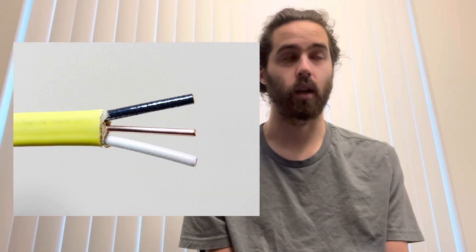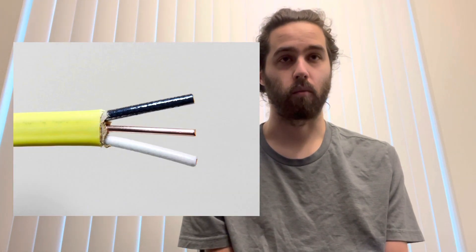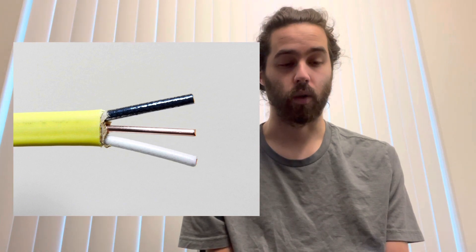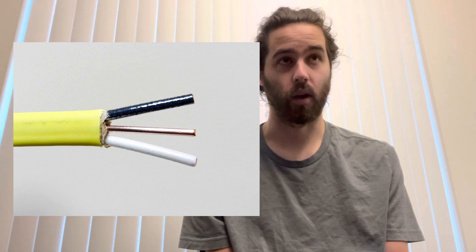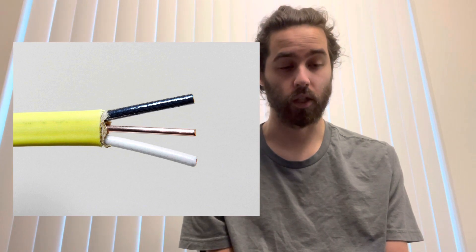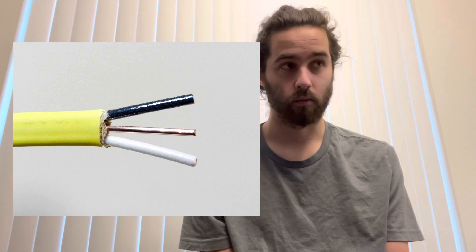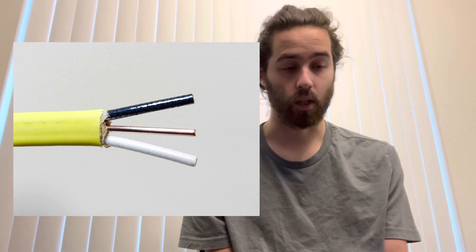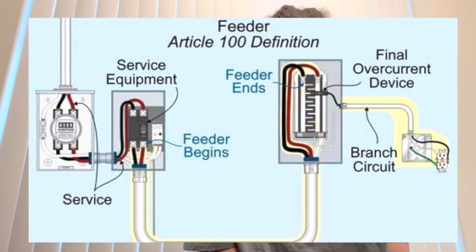Then you've got your hot, neutral, and ground, which are inside the wire — inside your Romex. You've got your black wire, which is your hot; your white wire is your neutral; and your ground is usually the bare wire. In a commercial application, the ground will be in a green coating of plastic insulation. Then you've got your feeder, which goes into the panel. The wire going into the panel is called the feeder, powering up the panel.